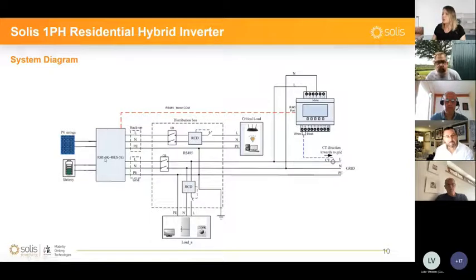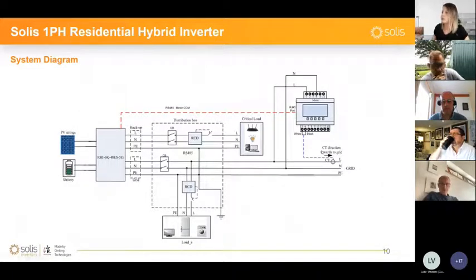the hybrid inverter will send a control command and it will start charging the battery with that excess of energy, just in order to get this value for energy being exported to the grid as close to zero as possible. So it will not waste any kind of energy. Of course, if the batteries are full and there's no room left, that energy will flow back into the grid if it's not consumed by the load.